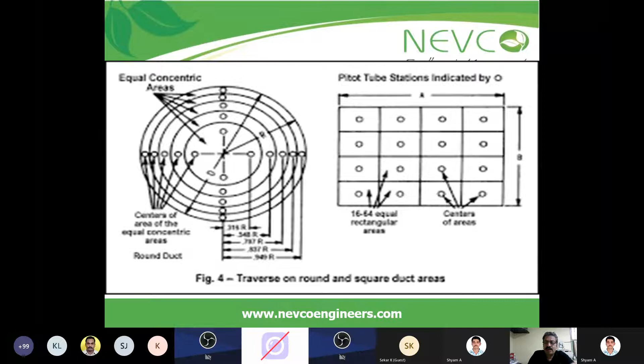Okay. And this is the pitot tube, showing how to traverse in a round duct or in a square duct. In the square duct, for the number of measurements, you have to take 16 to 64 equal rectangular areas. You have to divide, measure each, and take an average of that. With this diagram, you can see the traversing in the round and square duct areas, how to take measurements from one end to the other. Then you will get an accurate flow measurement.